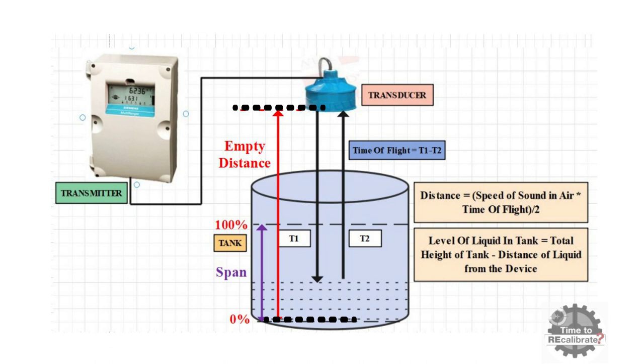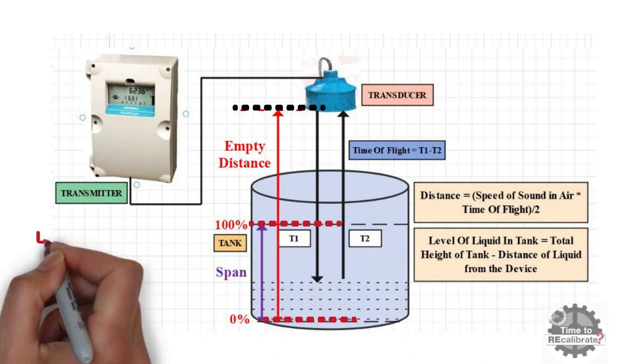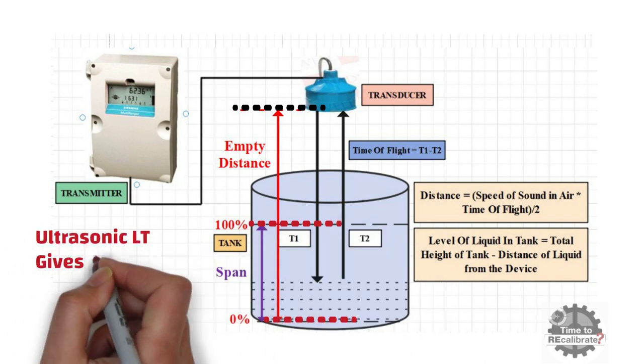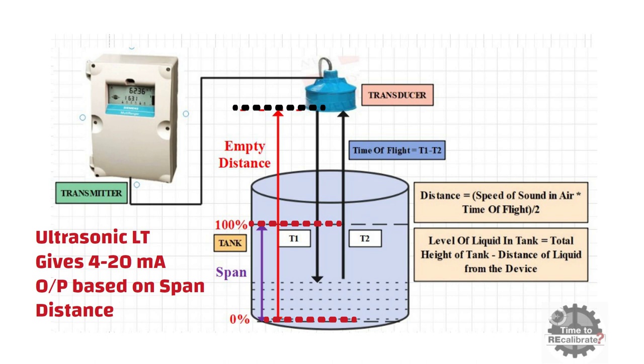Second important term is span. Span is the distance from 0% level of the tank to 100% level of the tank. Any ultrasonic level transmitter gives 4 to 20 mA output based on span distance. You have to have correct span value for accurate level measurement in ultrasonic level transmitter.